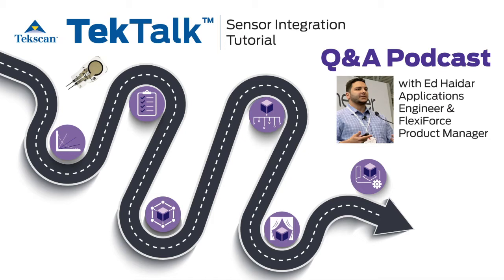Similarly, if you take one of our 100 pound sensors, you could get that sensor to operate in the thousands of pounds by altering reference voltage or feedback resistance or the circuit gain itself. So there's quite a bit of flexibility in terms of the force range you can get out of one sensor.